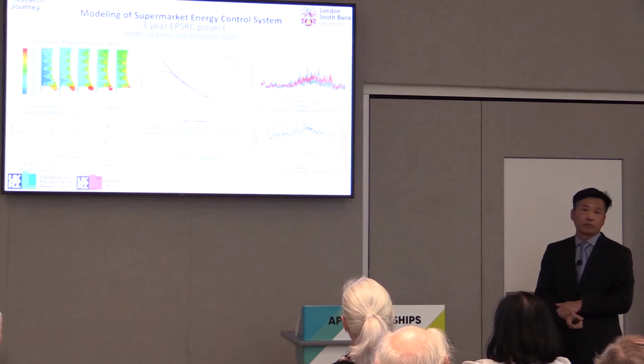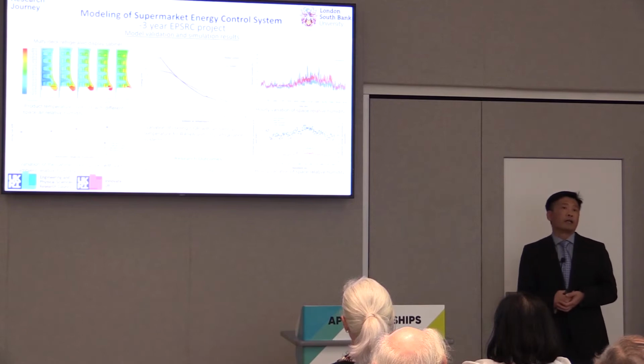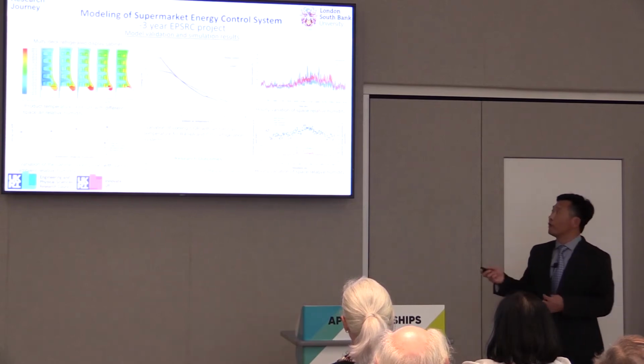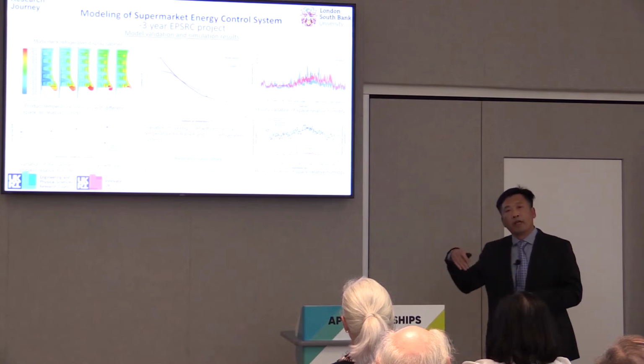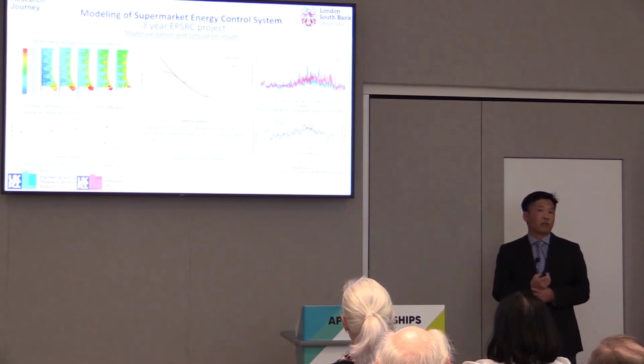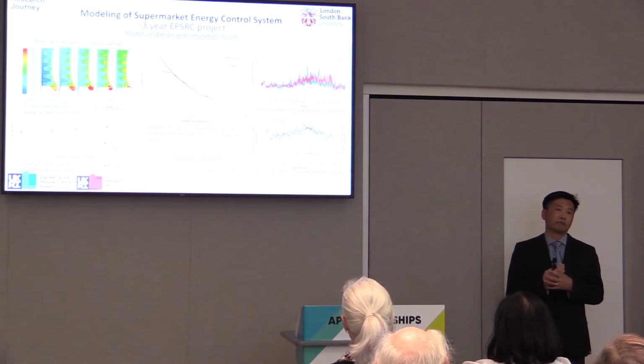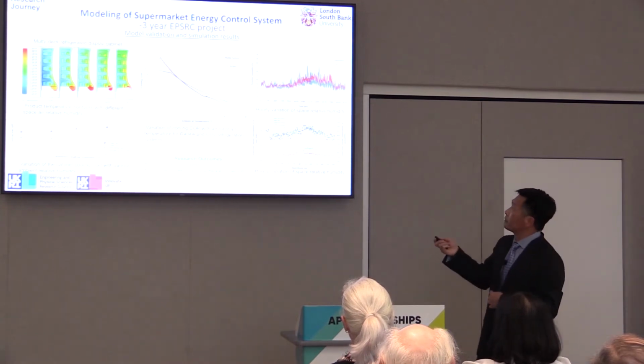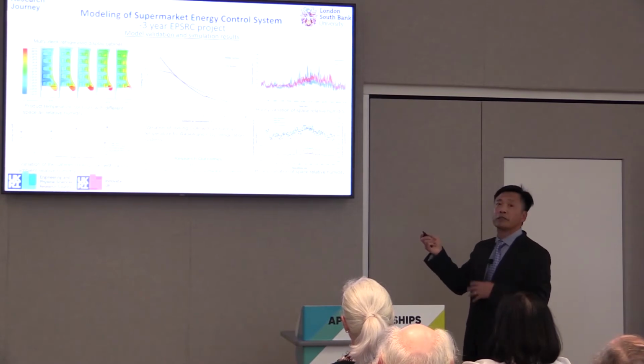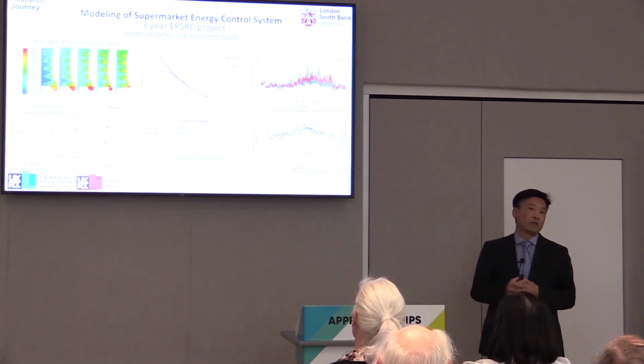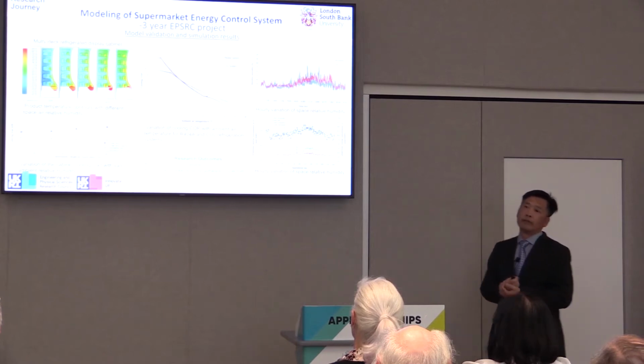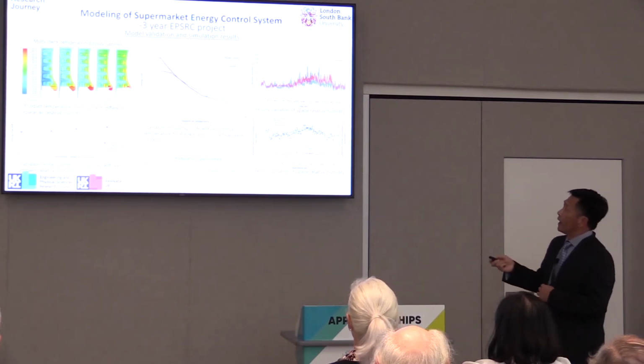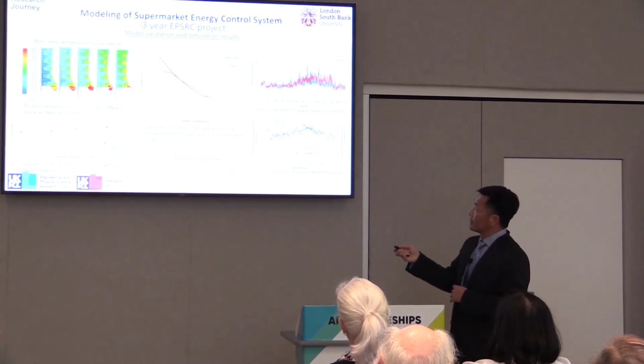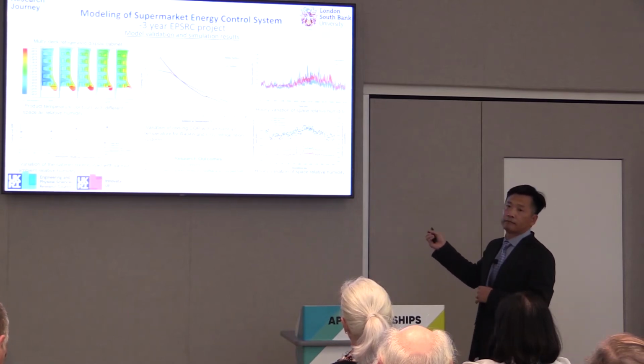So once the model has been validated, it can have quite significant applications. One example of the model application is to evaluate and compare the refrigeration system performance when different refrigerants are used. We select two different refrigerants. One is R448, which is the currently used refrigerant. The other is CO2, the future refrigerant for the supermarket. And we can compare the COP, which is the efficiency of the refrigeration system, at different ambient air temperatures.